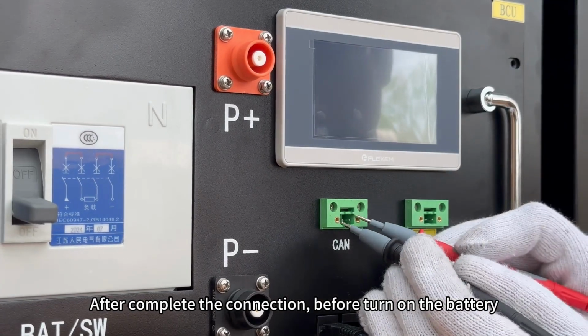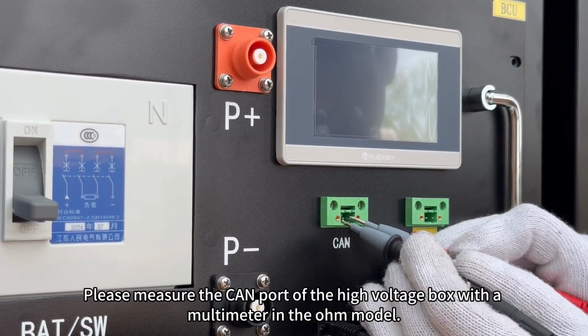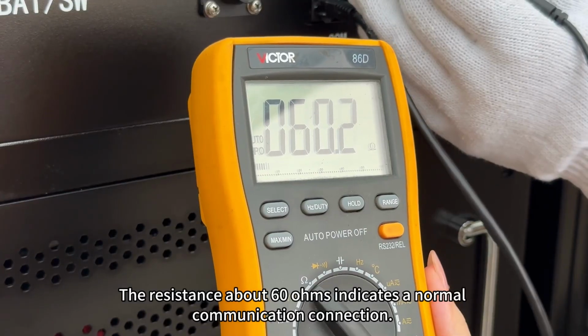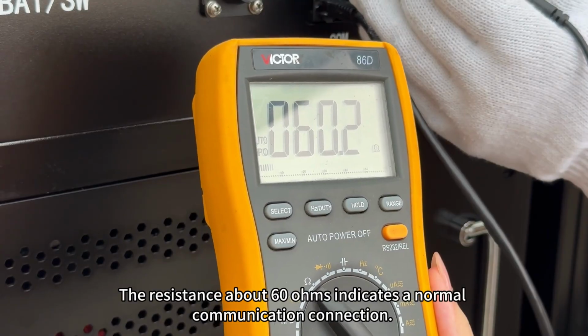Communication connection check: after completing the connection, before turning on the battery, please measure the CAN port of the high voltage box with a multimeter in ohm mode. A resistance of about 60 ohms indicates a normal communication connection.